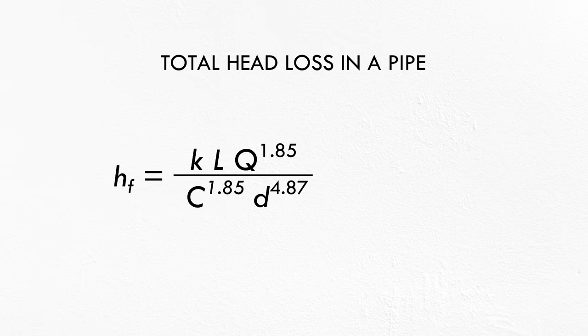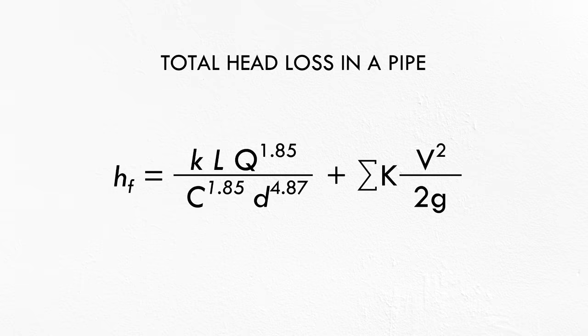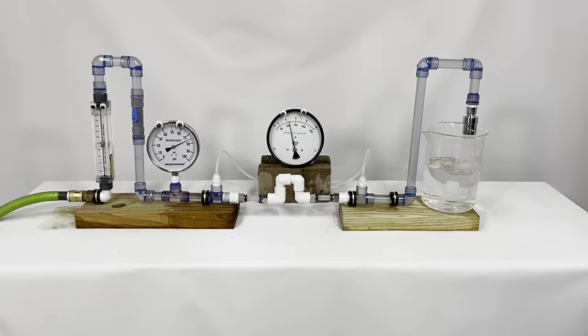Engineers have to include minor losses to the calculated frictional losses within the pipe to estimate the total head loss. In my demo here, except for the case of the 20-foot pipe, most of the pressure drop between the two measurement points is caused by minor losses through the different fittings in the manifold.